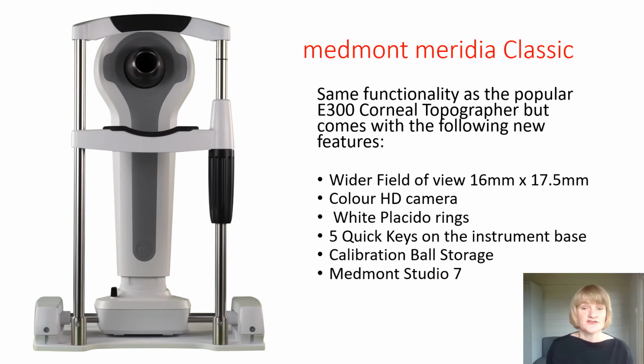So looking at the features of the classic model, it has the same functionality as the popular E300, but it does have some additional features. It has a wider field of view than the E300 at 16mm by 17.5mm. The black and white camera has been replaced with a colour camera, and we now have white Placido rings. There are 5 quick keys on the instrument base, which we'll look at further in other presentations. These allow you to operate the machine from the instrument itself, rather than having to go back to the mouse and keyboard of your PC.